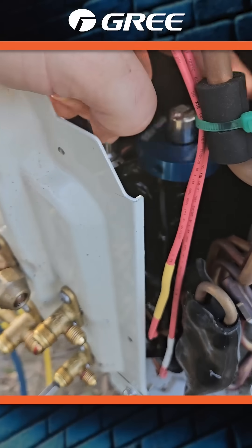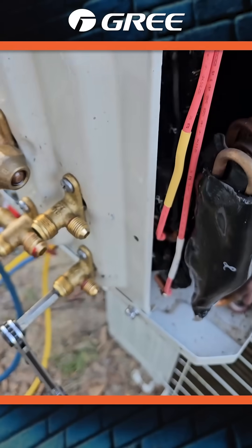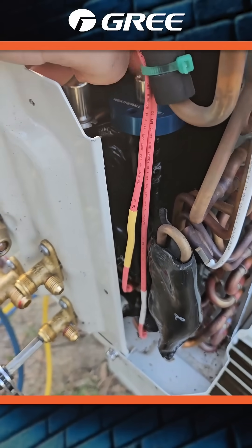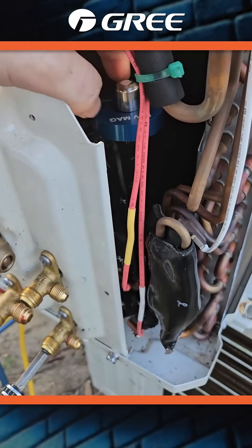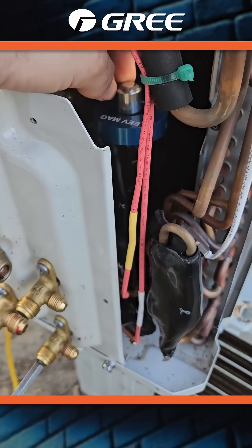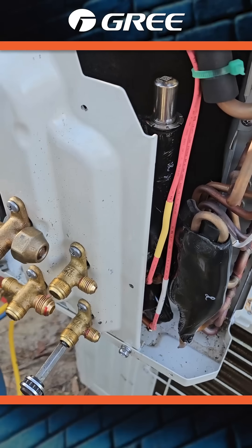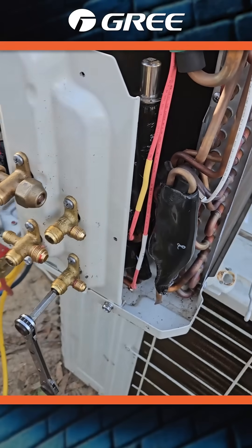Spinning it either way, nothing. So I believe some of that Loctite that was used on the flares actually got into the EEV and has locked up the piston inside there.